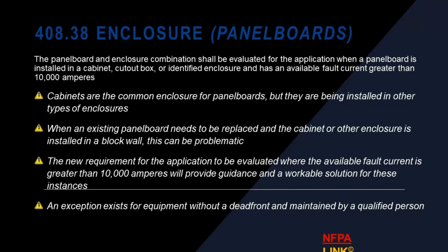So another change for 23, 408.38, enclosures, panel boards. The panel board enclosure combination shall be evaluated for the application where the panel board is installed in a cabinet, cutout box, or identified enclosure and has an available fault current greater than 10,000 amps. This is what we're going to concern ourselves with.